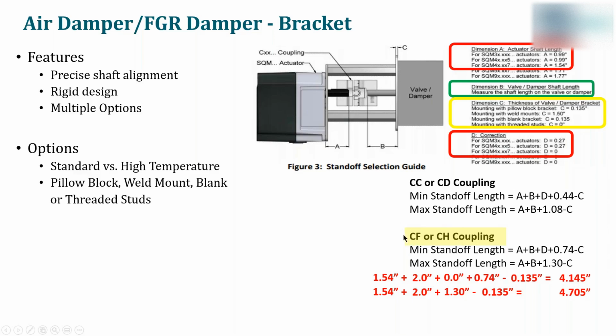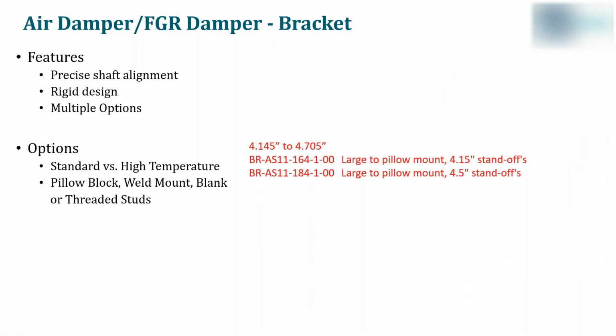Since we are using a CF or CH coupling, I calculated the minimum standoff length and the maximum standoff length using this equation, which is in our literature. And that length comes out to 4.145 inches for the minimum, and 4.705 inches for the maximum. Based on that information, these are the two brackets that will fit in this application. Now, if you use a shorter bracket, this could result in binding. If you use a longer bracket, chances are that the actuator and damper will not be coupled properly.